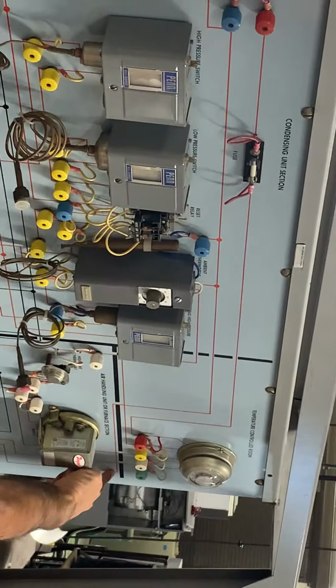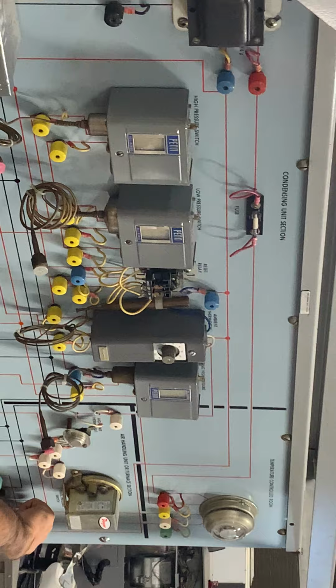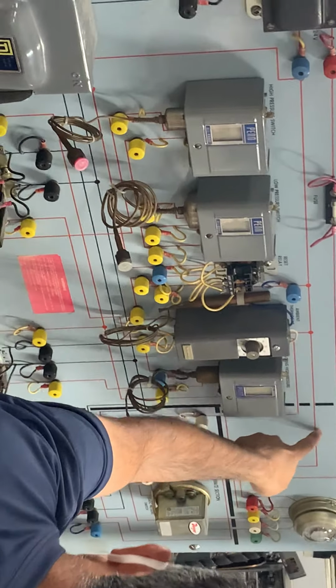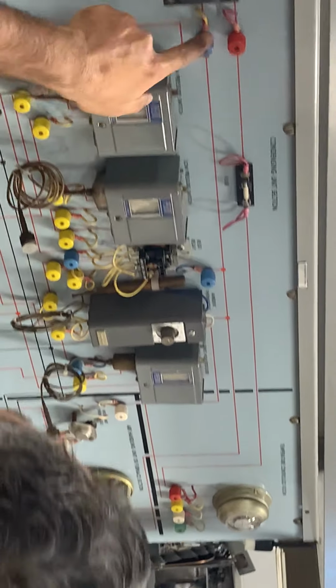That is the simplest circuit in this board. We go red to the fuse, to the thermostat, to the relay coil, and back to common. On this particular board, blue is a 24 volt common. That is the simplest circuit on the board.